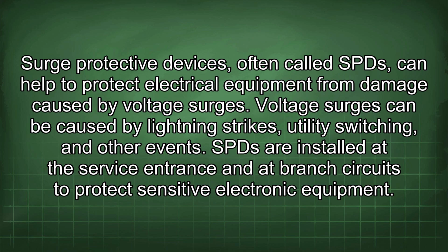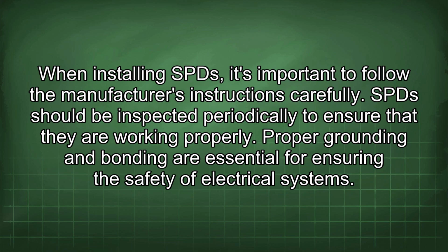Surge protective devices, often called SPD, can help to protect electrical equipment from damage caused by voltage surges. Voltage surges can be caused by lightning strikes, utility switching, and other events. SPD are installed at the service entrance and at branch circuits to protect sensitive electronic equipment. When installing SPD, it's important to follow the manufacturer's instructions carefully. SPD should be inspected periodically to ensure that they are working properly.